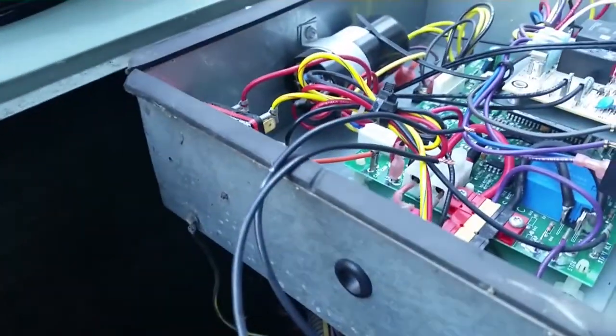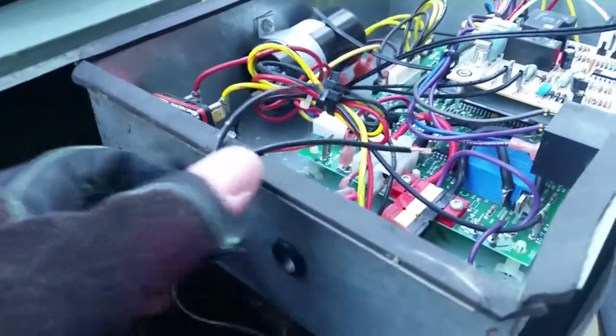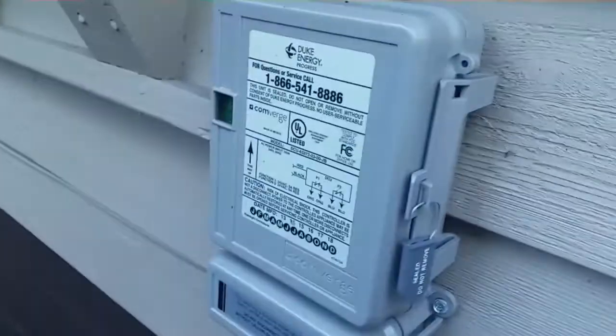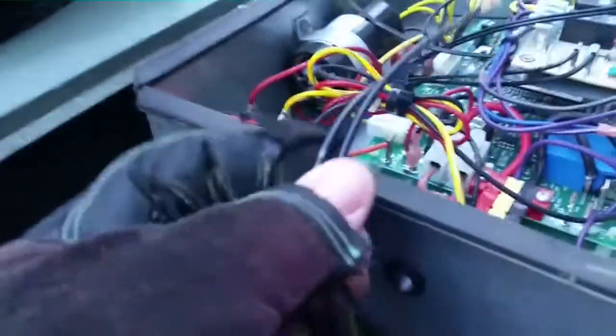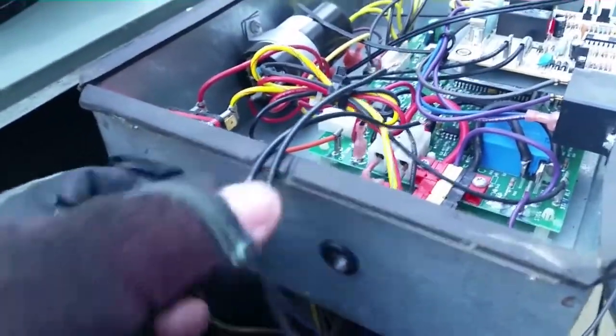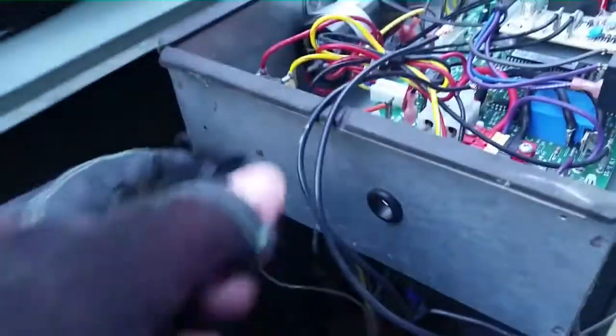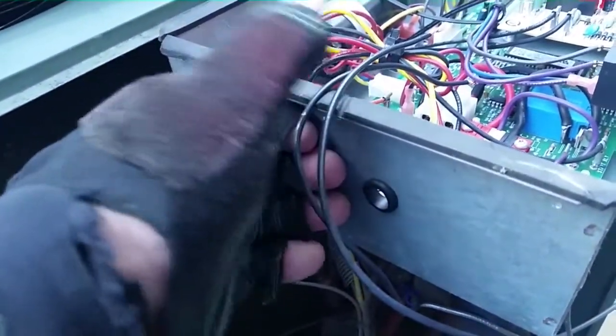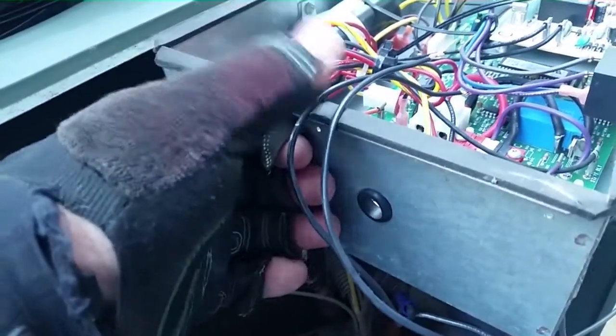We're checking out a couple systems here. Here's a Rheem 15 SEER system, I think it is, from 2009 or 10. We had our power wires from the Duke Energy box here laying right across the top, sandwiched between this and the metal top. Not a real good idea, even though it's gasketed here. The top is not, and it could definitely short out against the top.